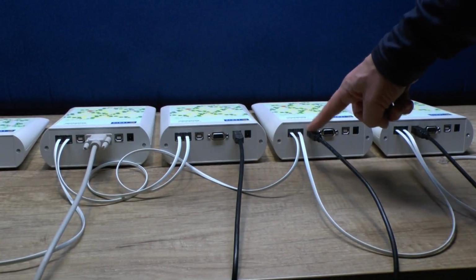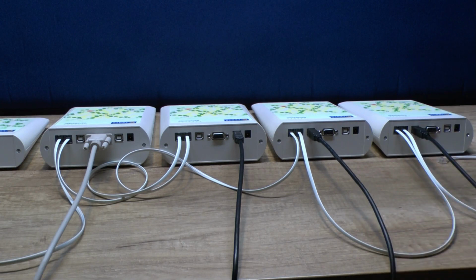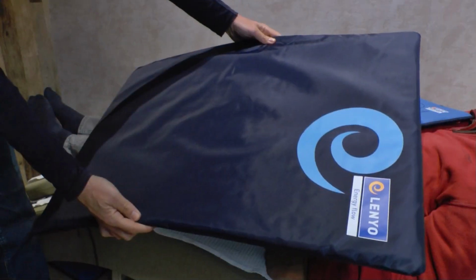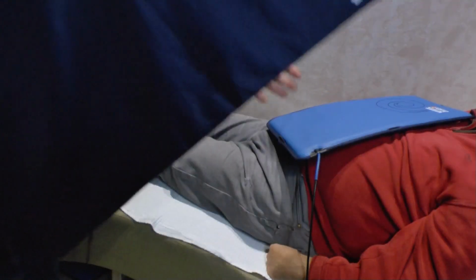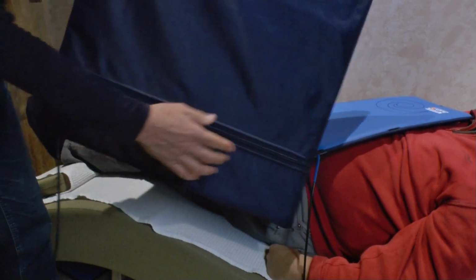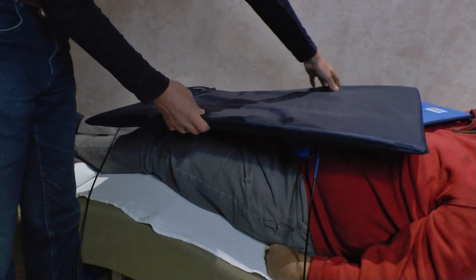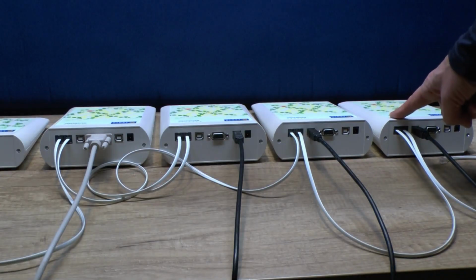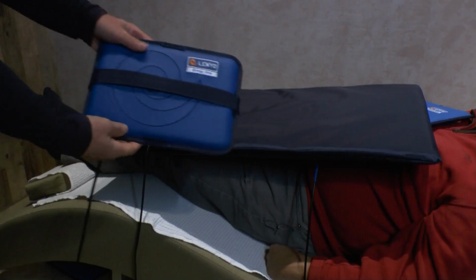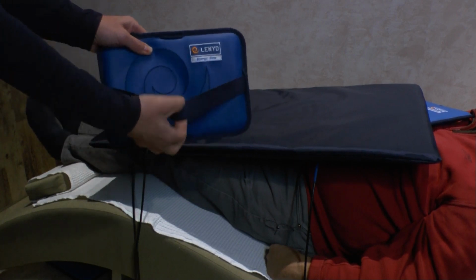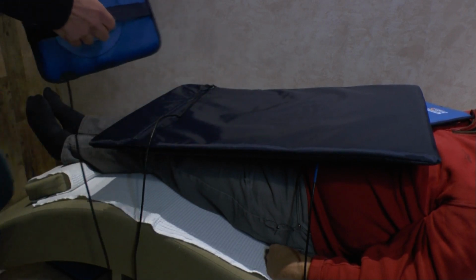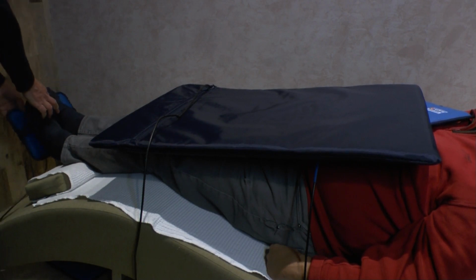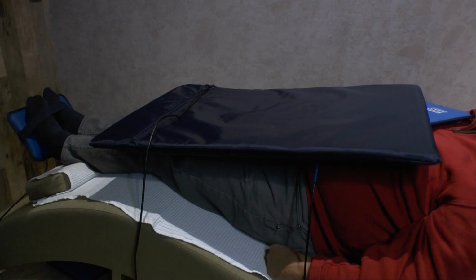An L-sized antenna is typically used with channel C. This mat usually covers the stomach and pelvic area and extends down to the thighs. It is best to place it with the zipper side facing up and towards the feet. Channel D typically utilizes a small-sized antenna. We commonly position it against the soles of the feet, fixing it by the attached Velcro. The orientation of the mat, whether it's the front or back side facing the feet, is not important.